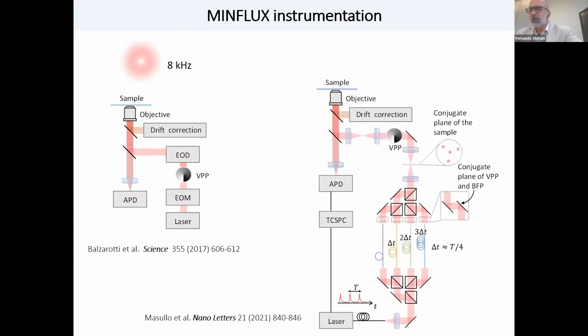Later, we came up with this other configuration, but it looks more complicated, but in fact, it's easier and more convenient. And this is called a pulsed interleaved MinFlux. So what we did here is to take a pulse laser, we split the laser beam in four, and to each of these new beams, we introduce a delay of a quarter of a period. And then we recombine those beams again. We apply the phase modulation always to obtain the focus with a central zero of intensity. And now by displacing these four beams in space on the sample plane, we can perform the MinFlux measurements at a much faster rate, actually at the repetition rate of the laser. That means we can perform MinFlux measurements at 20 or 40 megahertz. And this is now the maximum speed that you can achieve. And it's actually, it provides measurements that are limited just by the count rate of your label tag.